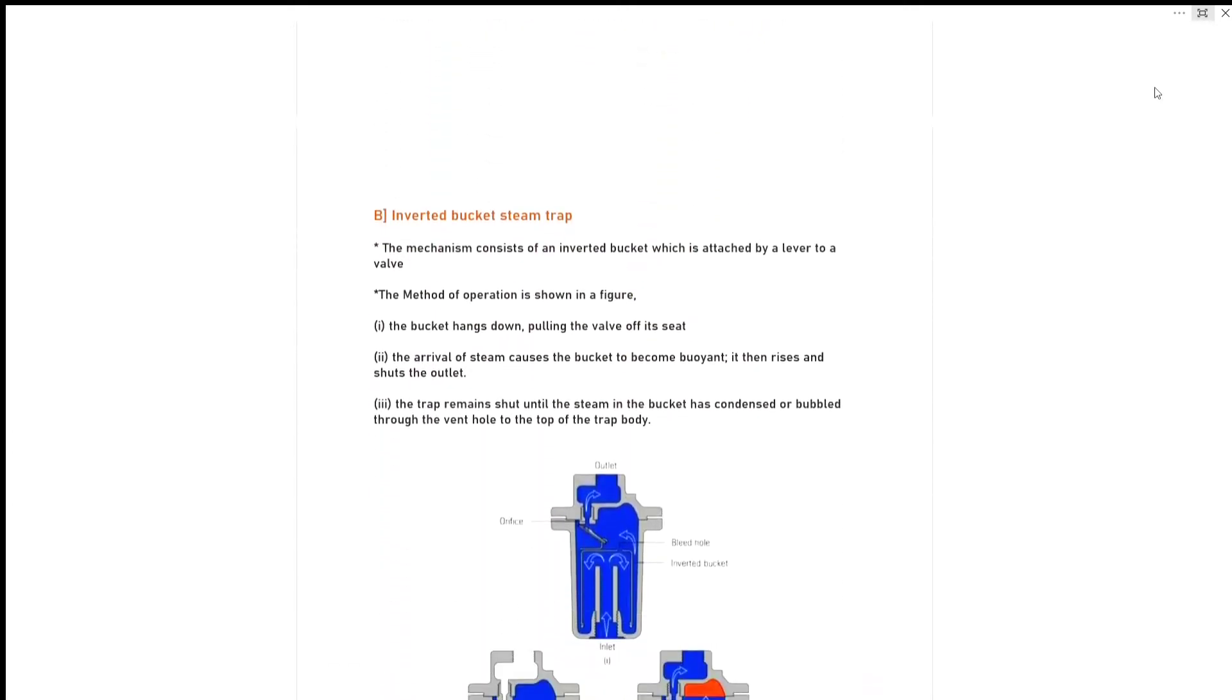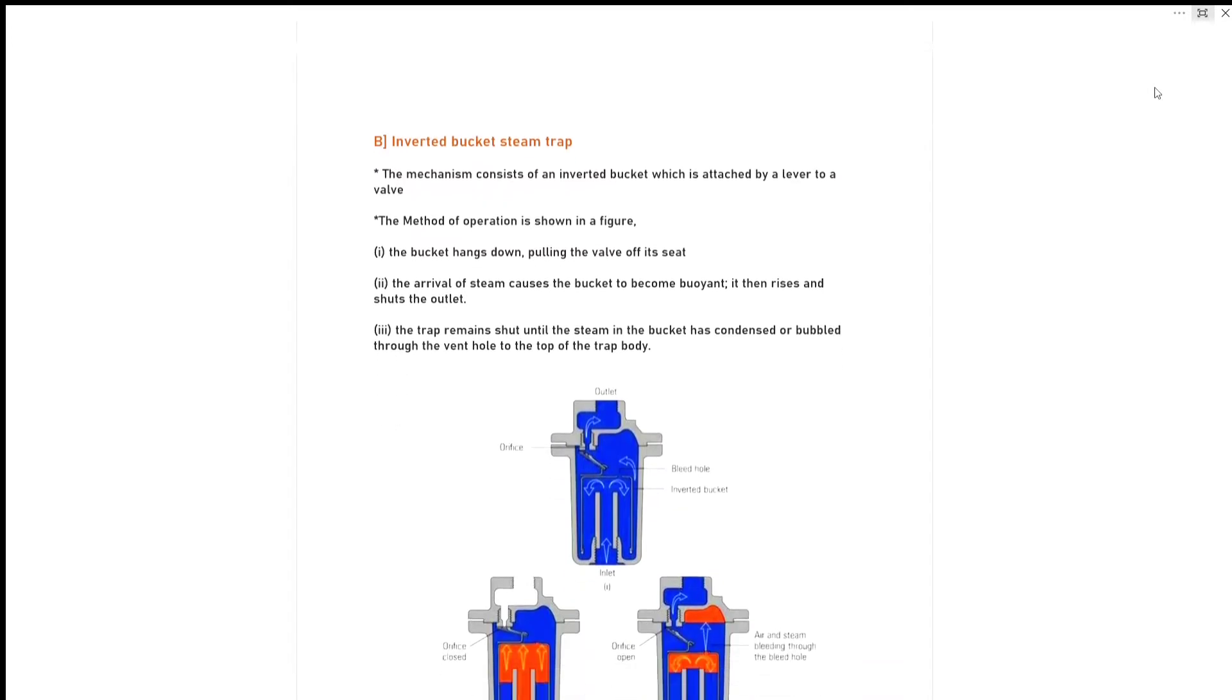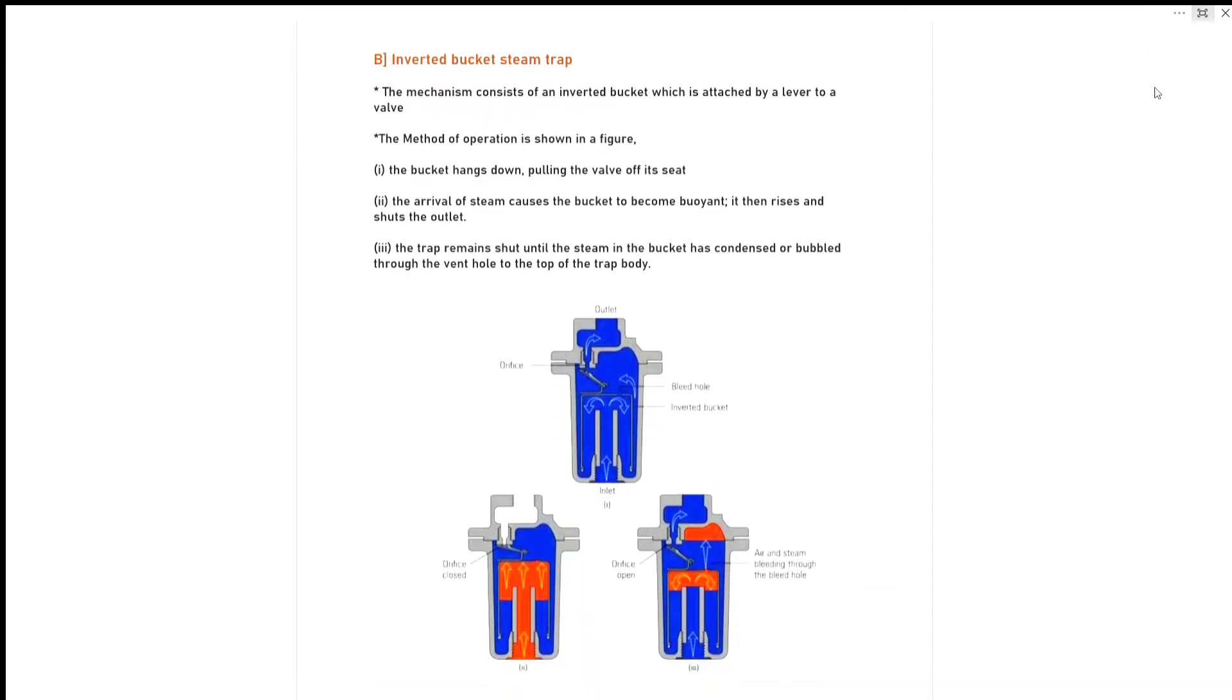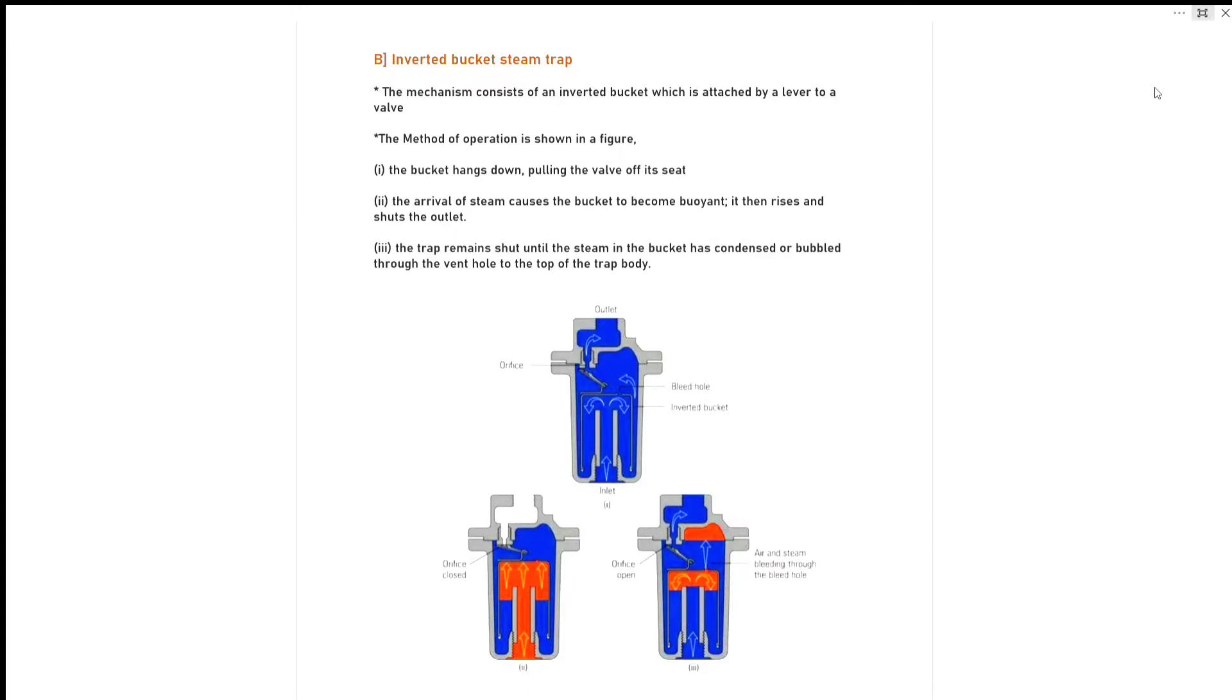Second one in mechanical steam trap is inverted bucket steam trap. The mechanism consists of an inverted bucket which is attached by a lever to a valve. The method of operating is shown in figure - you can see three figures here. First: the bucket hangs down pulling the valve off its seat. Second: the arrival of steam causes the bucket to become buoyant, then it rises and shuts the outlet. Third: the trap remains shut until the steam in the bucket has condensed or escaped through the vent hole to the top of the trap body.